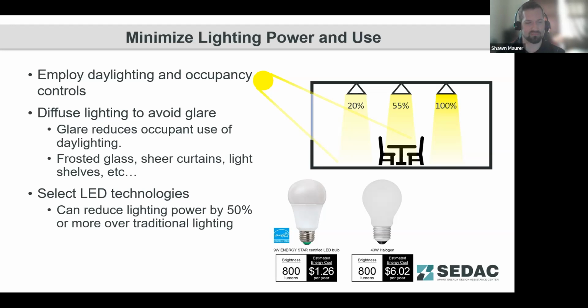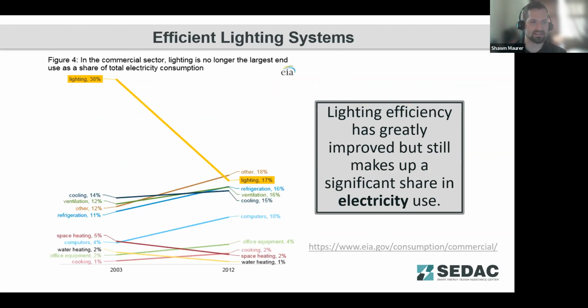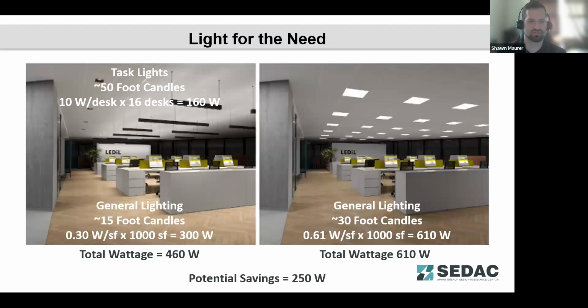But they can reduce lighting power by 50%, and we've seen some that can reduce lighting up to about 70%. So there's a bit of a range there. But that high efficiency lighting is going to do a lot to reduce not only your lighting consumption loads, but all that light that's used in the space also ends up as heat in the building. And so the more you can reduce your lighting loads, the less cooling capacity you need for the structure. We've done a lot to improve lighting efficiency, as you can note here, but it still makes up a significant share of our electric use. And so that's where we start touching on controls and lighting design.